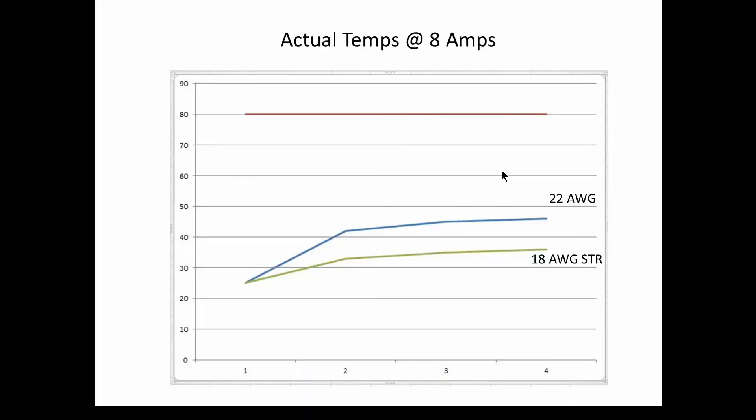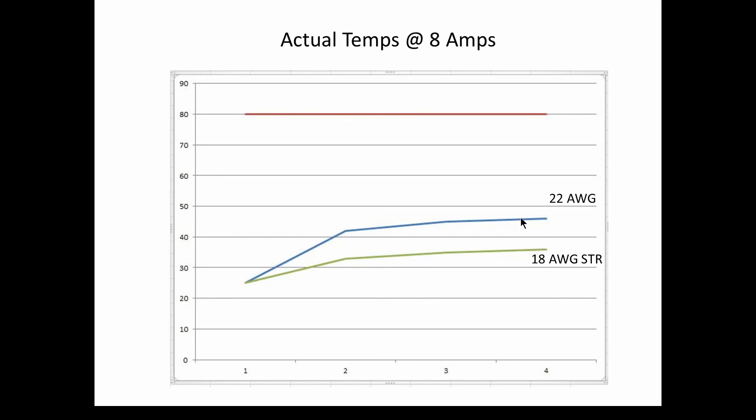Okay, so here's the chart I developed showing temperature versus time. I've got time on the x-axis and on the y-axis I've got degrees centigrade. And up at 80, that is the PVC, presumably the thermal temperature limit of the PVC. And these two graphs down here, I've got the actual measured temperature over time of the 22 AWG and the 18 AWG stranded. And as we saw, it takes a few minutes to get up to the final temperature. And in both cases, those temperatures are much below what we would expect based on the ratings table.